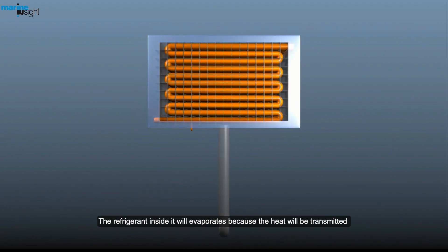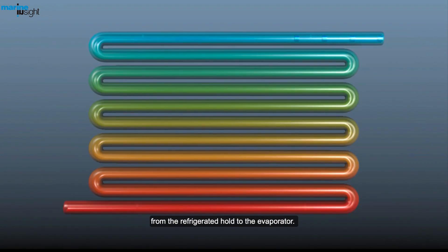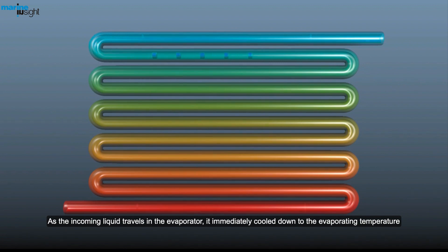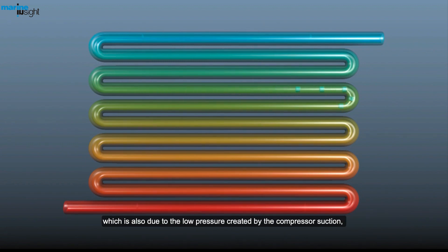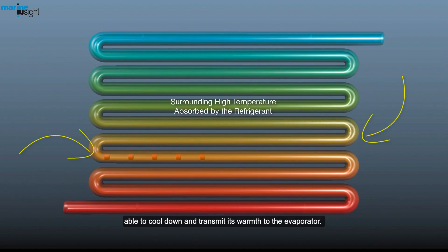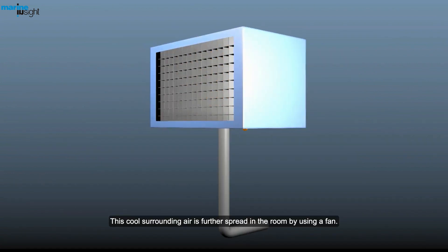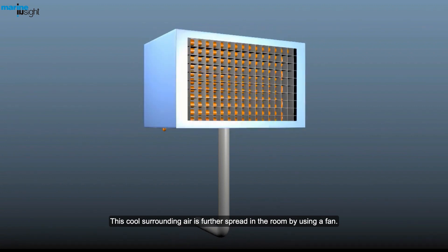The refrigerant inside it will evaporate because the heat will be transmitted from the refrigerated hold to the evaporator. As the incoming liquid travels in the evaporator, it immediately cools down to the evaporating temperature, which is also due to low pressure created by the compressor suction. With the result that the surrounding air from the hold at a higher temperature is able to cool down and transmit its warmth to the evaporator. This cool surrounding air is further spread in the room by using a fan.